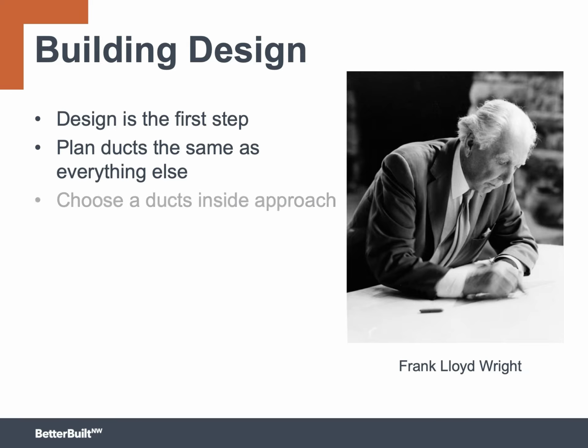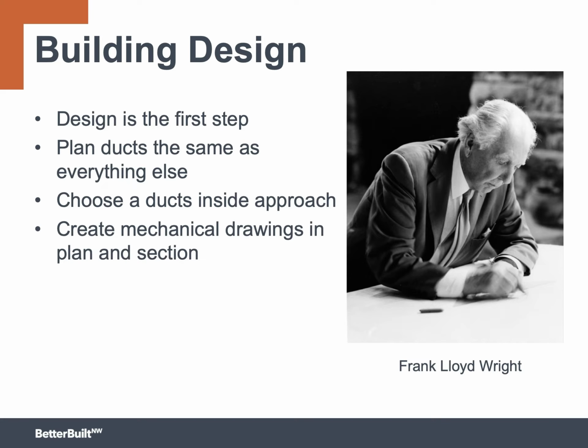The first step is to choose the strategy that you plan to use. Is it going to be the dropped soffit, or the open web floor trusses, or something else? Or maybe it will be a combination of approaches. Then create mechanical drawings, not only in plan view but also in section, so that it's very clear exactly where the ducts are going to occur inside the house. In doing this, you'll want to consult the HVAC contractor because they're going to help you understand the size of the ducts that are needed and some of the limitations, perhaps on the way the ducts have to run, the fittings and the grills, etc.